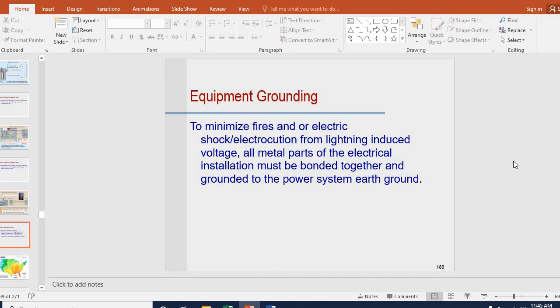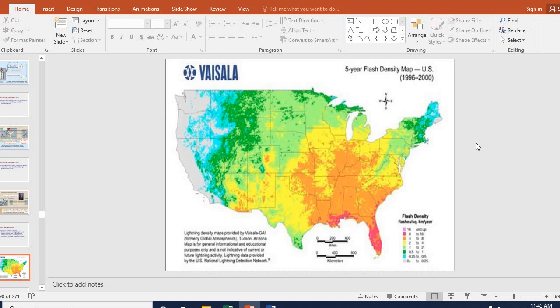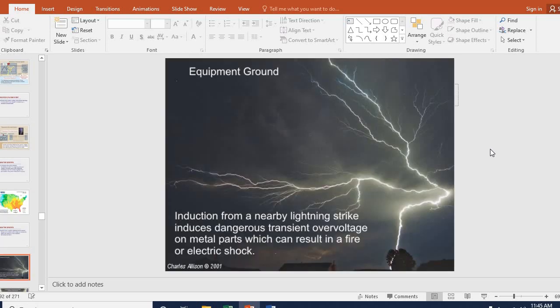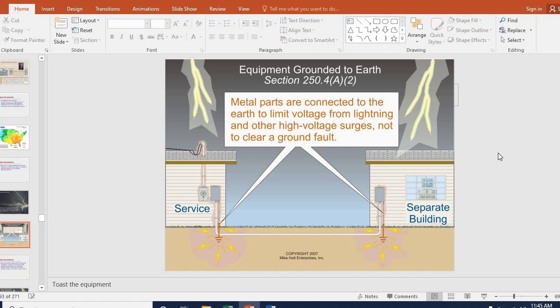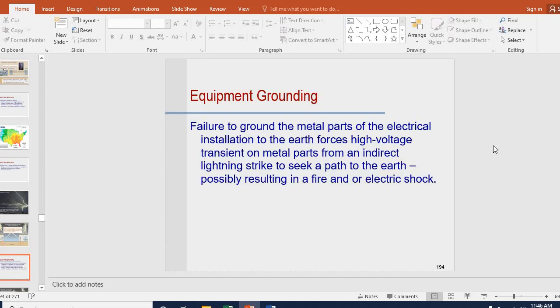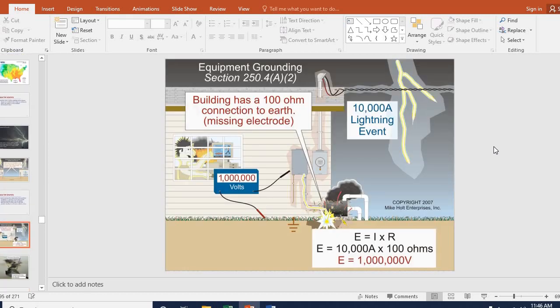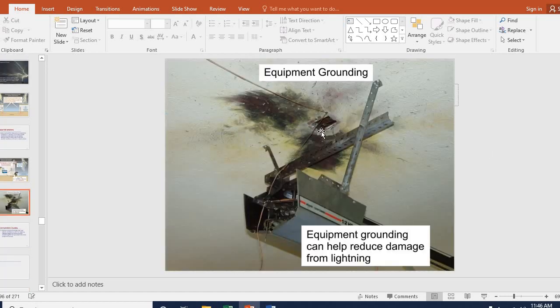To minimize fires and electrical shock or electrocution from lightning induced voltage, all metal parts of electrical installation must be bonded together and grounded to the power system earth ground. Metal parts are connected to earth to limit voltage from lightning and other high voltage surges, not to clear a ground fault. There's what happens when that equipment grounding can help reduce damage from lightning.